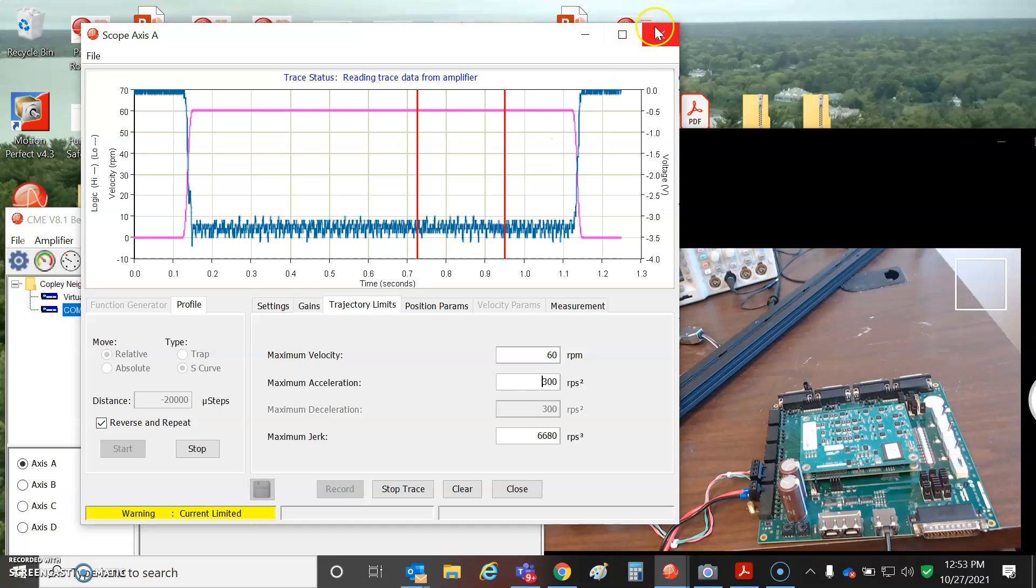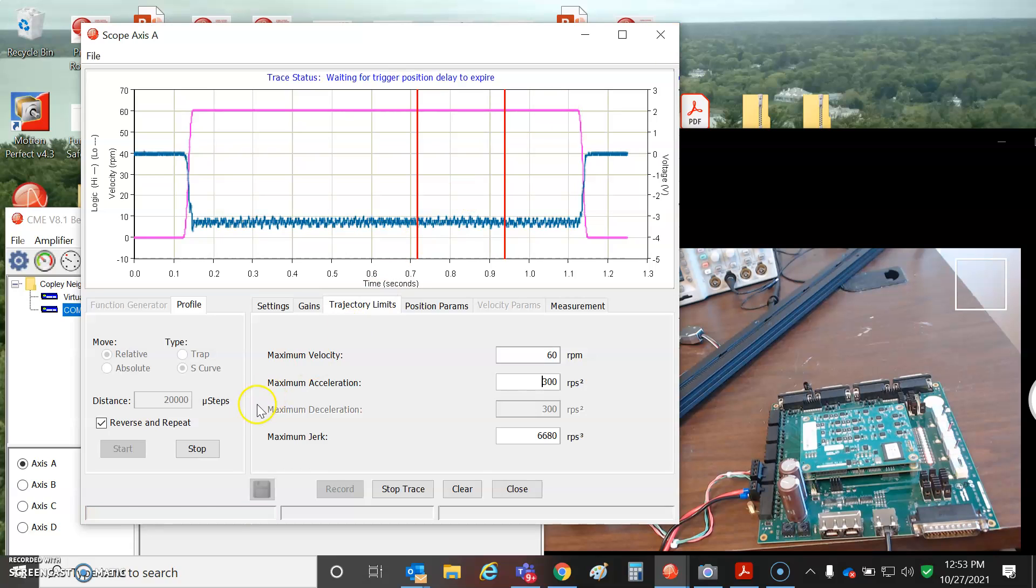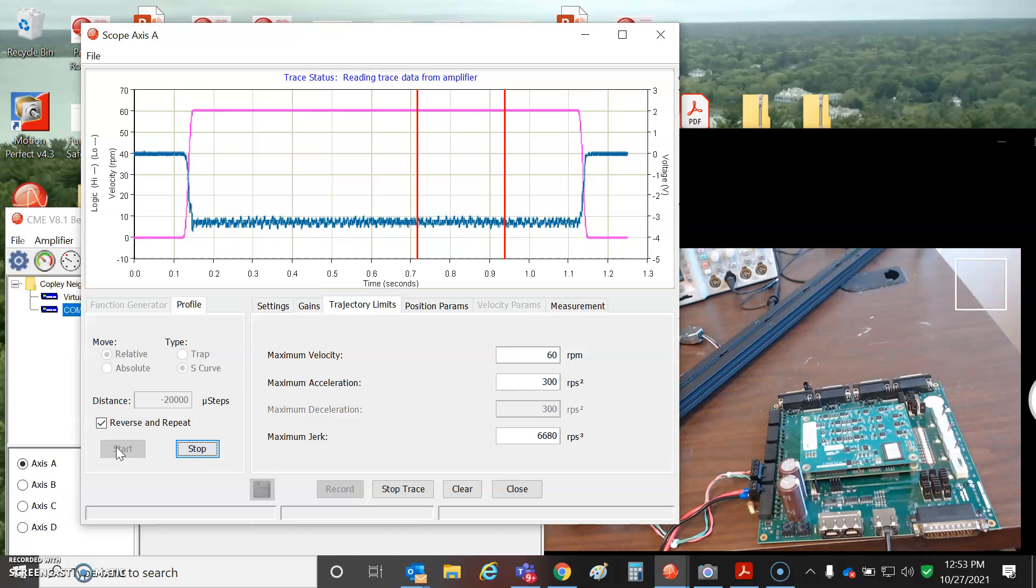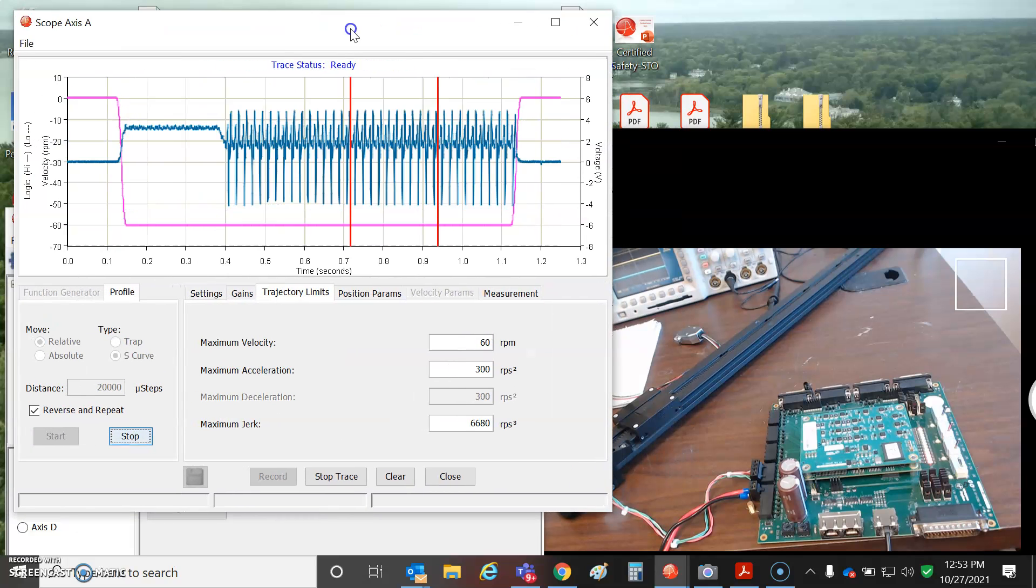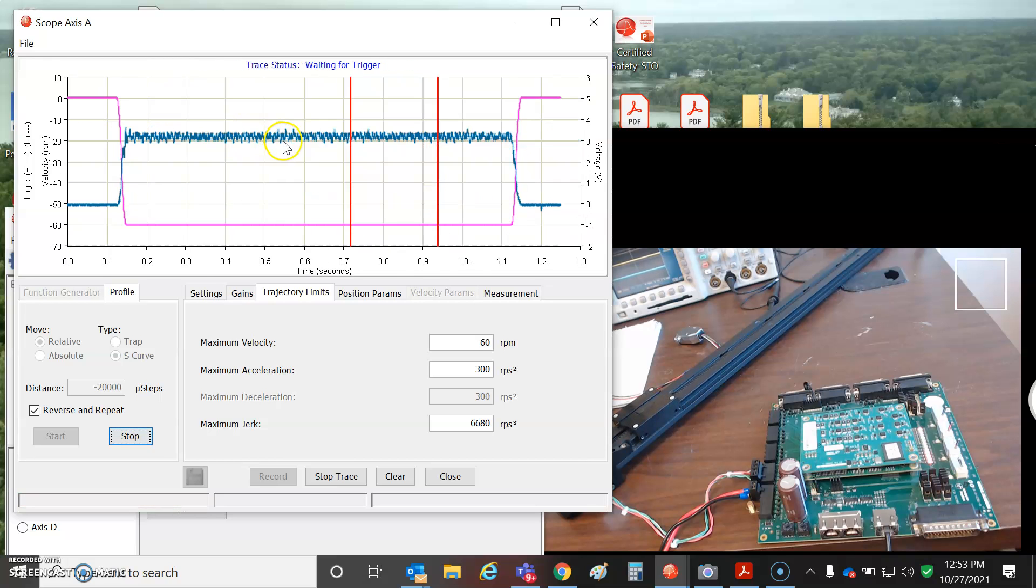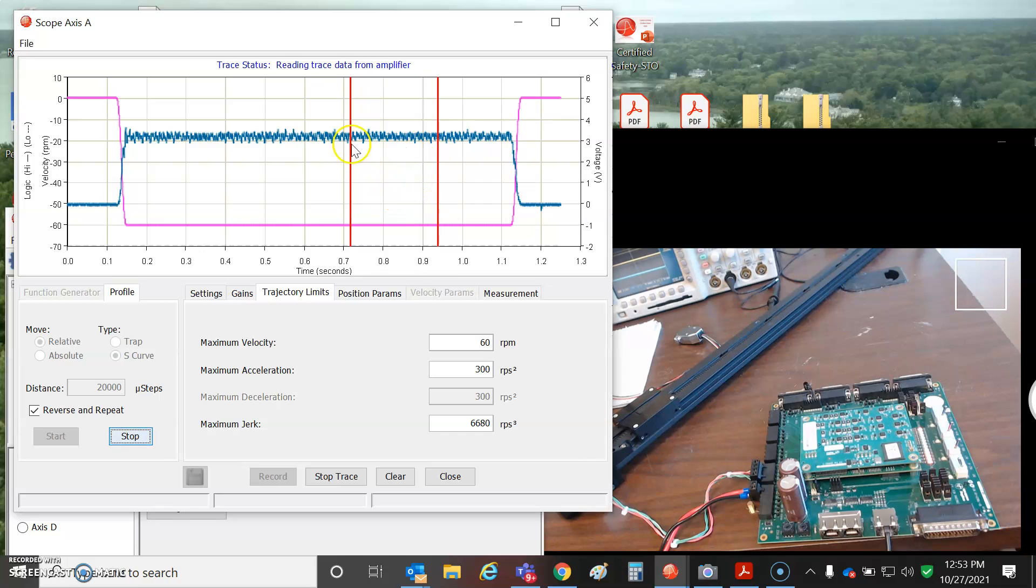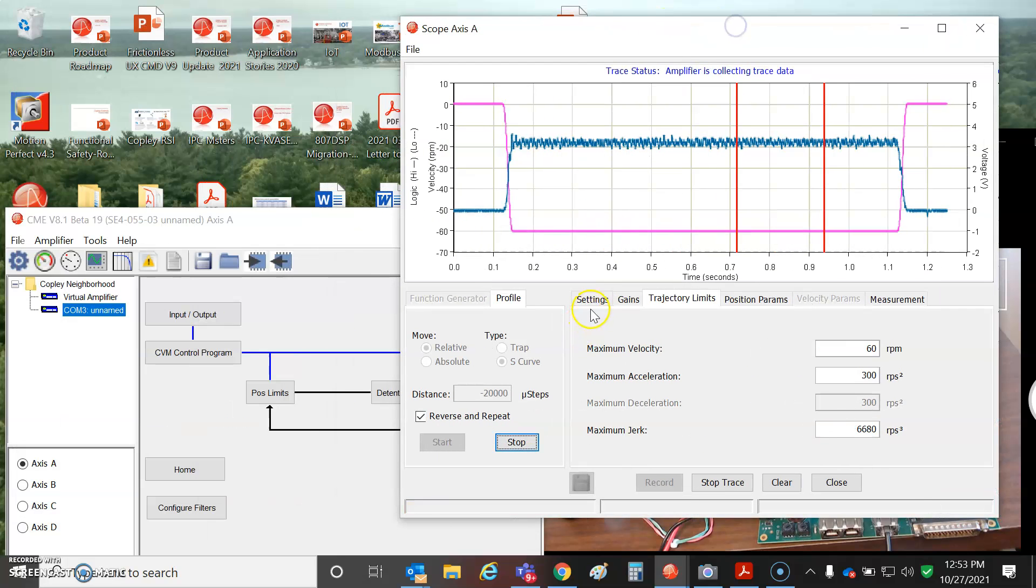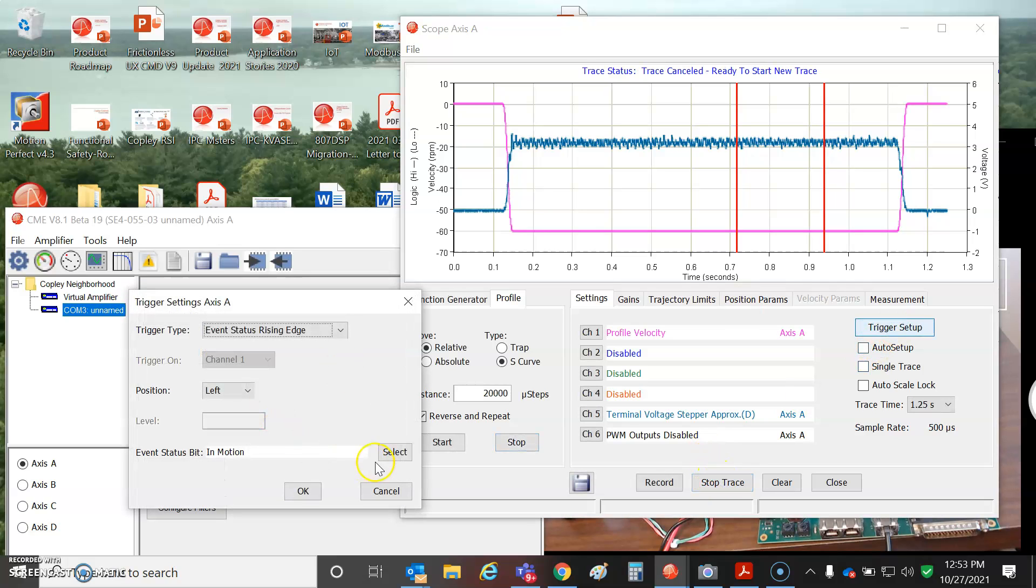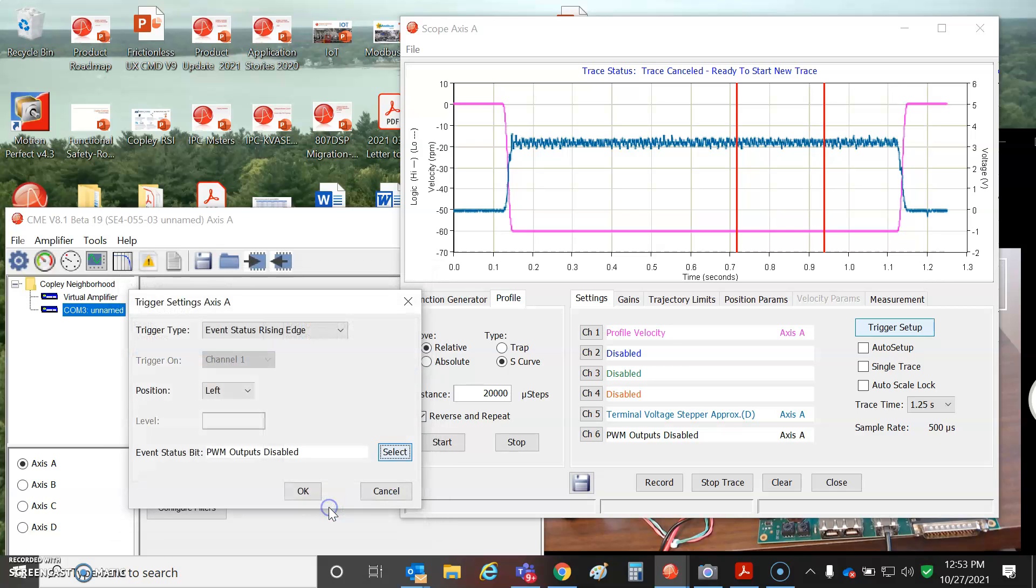So we'll take a look now at a CVM indexer program used to detect the stall. And of course, the stall occurs when you get into the hard stop, we hit the hard stop. And yeah, you can see the voltage is dropping. There it is. Drops in voltage plus definitely dropping when it's driving into the hard stop. But we'll see how fast we can detect that. My program's going to disable the drive output stage. So I'm going to trigger on the disabling of the drive.